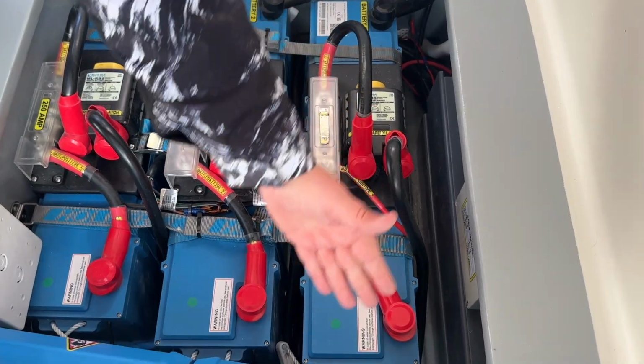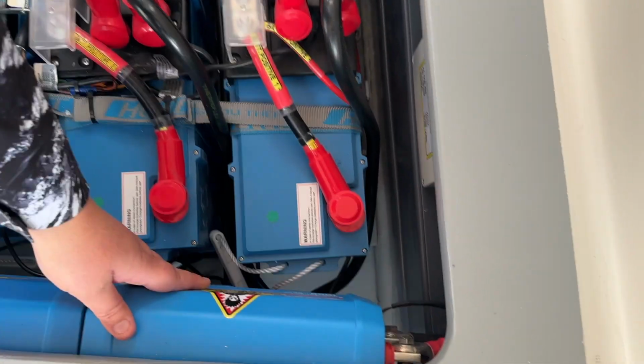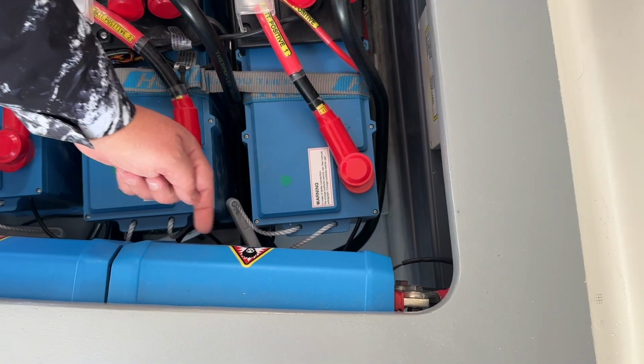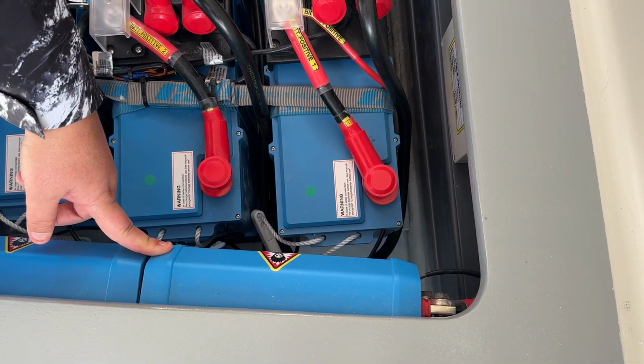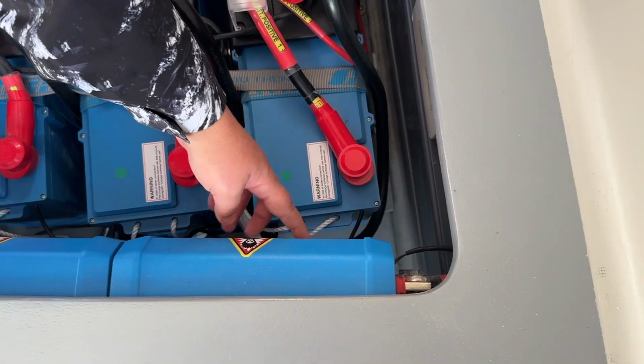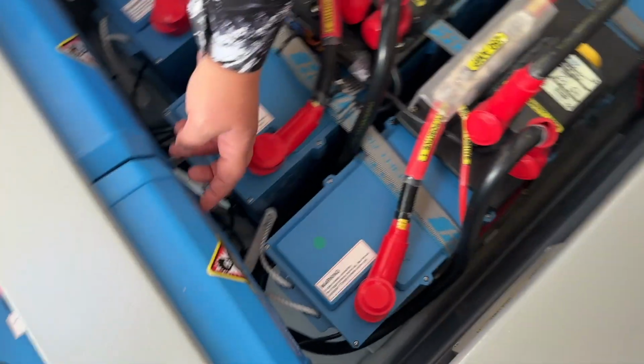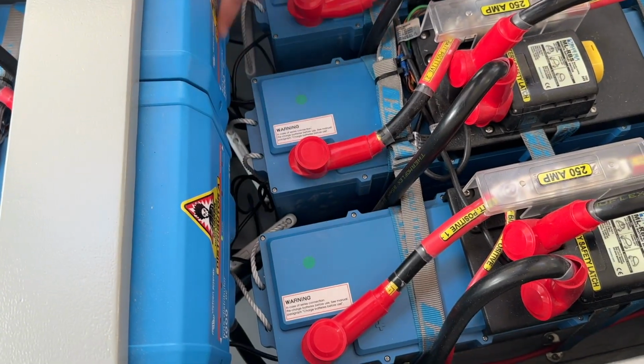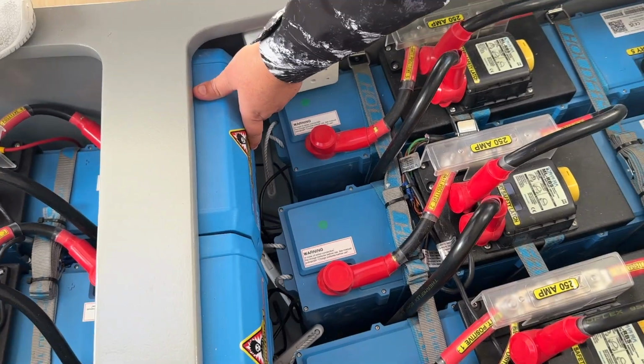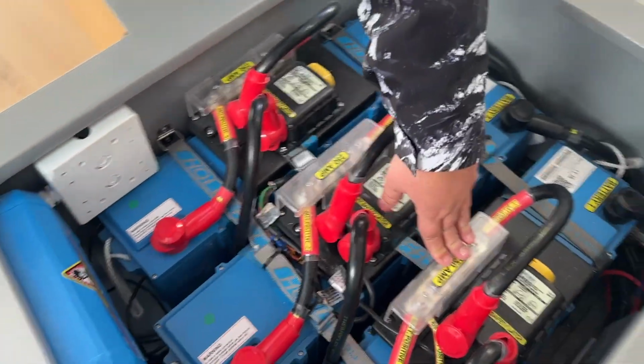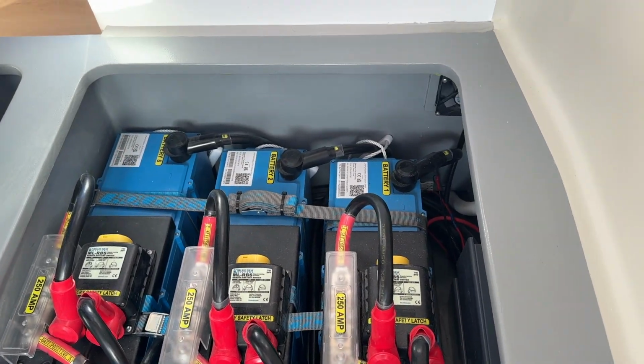From there you go into the lynx distributor, each one on a mega fuse, which is also a 250 amp mega fuse. These ones are activated in your system, so if you blow a fuse in this circuit here, you will get an alarm on your Victron system. If you lose the fuse connection, you will definitely hear it.